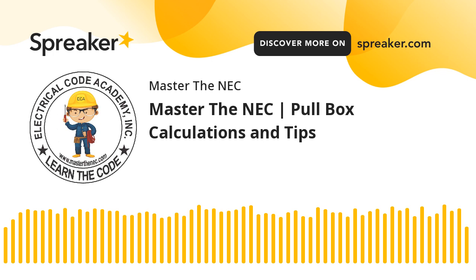Now, in the real world, that's different. In the real world, we're going to size our pull boxes based on what our condition is, whether we're coming in from the left or from the right or from the top or from the bottom of the box. Heck, we even have to determine if we're coming in from the back of the box and have a removable cover on the front. All those things are real world situations where we know how we're going to make these boxes. We know where we're going to put these raceways. You just have to know the code rules that are associated with it.